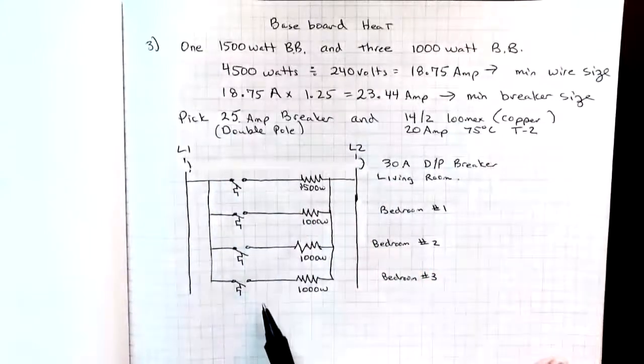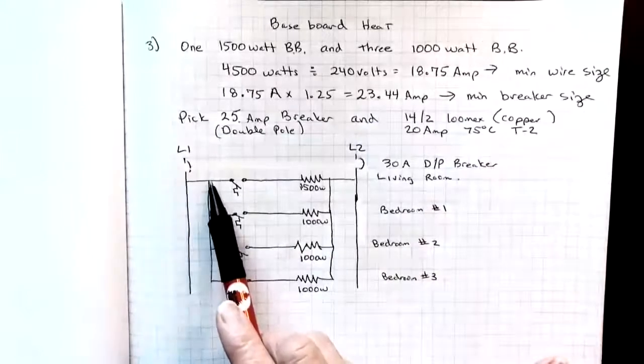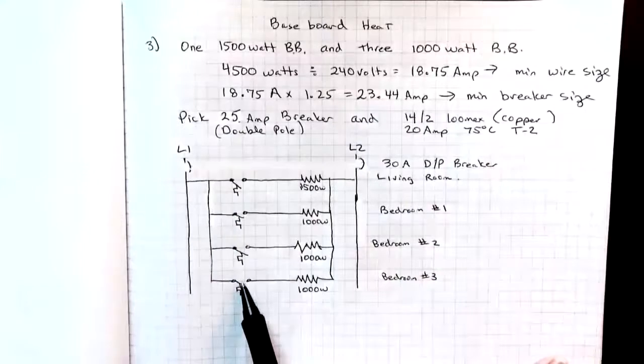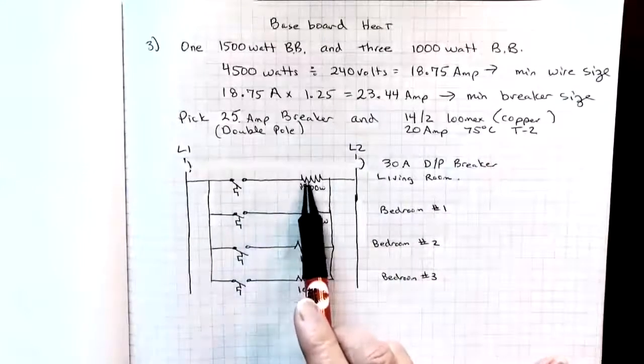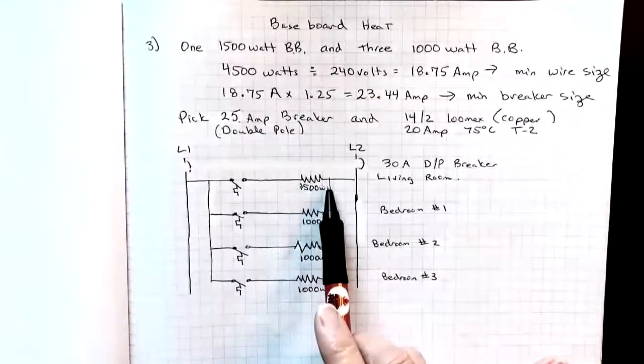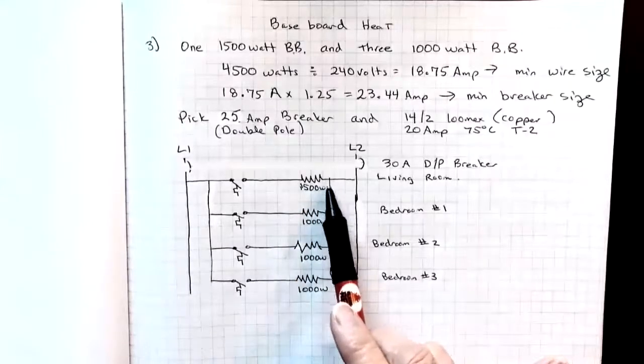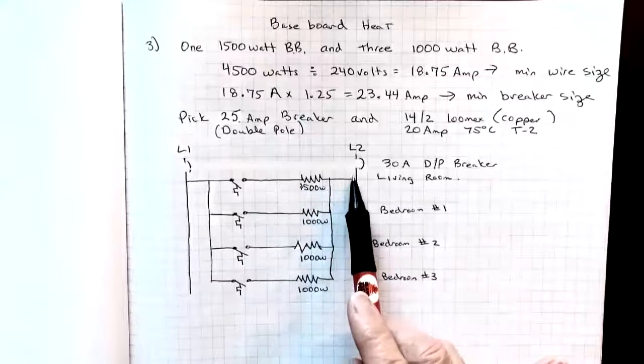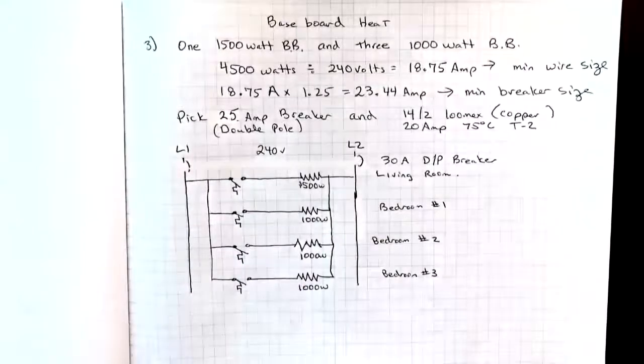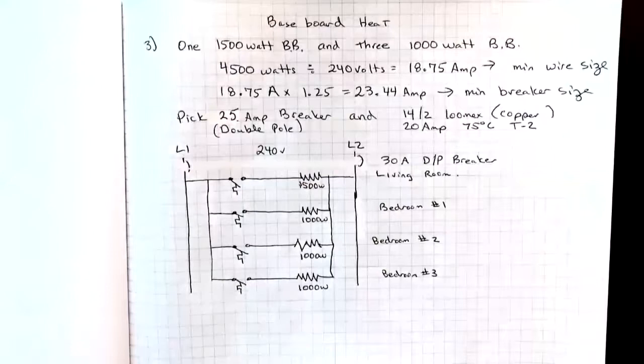This would be the schematic. So off of line one, we'd come and we'd split and go to four thermostats, one in each room. Each thermostat would have a switch leg that goes to its own baseboard heater. And then the neutral, it's not actually neutral, it's line two coming back because we actually have 240 volts between line one and line two for this installation. Hope that's helpful.